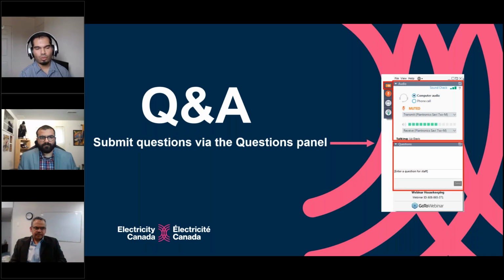But normally we test in 3 ways. You can test like you would using Omicron Quick CMC - you put in the values of currents and voltages and then just start and see how the fault occurs. That's one way. The second method is to create a state sequence file using the Omicron state sequencer, where you have multiple states - a pre-fault state, a fault state, and then a post-fault state.